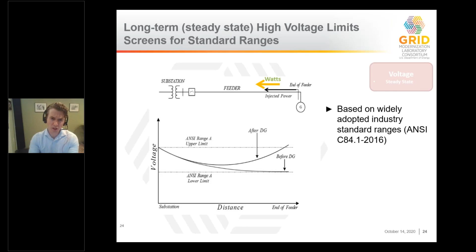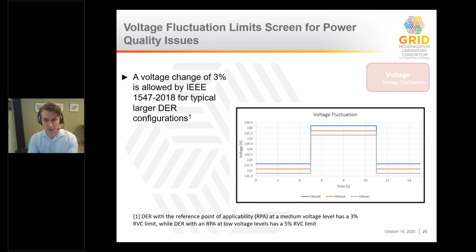Another voltage-related issue is the voltage change from a DER unit turning on versus off, sometimes called voltage fluctuation. The most relevant component here is the rapid voltage change limit — if there's an abrupt change in output, caused by various factors, even faster than something like cloud cover, there can be a step change in voltage that causes equipment problems.